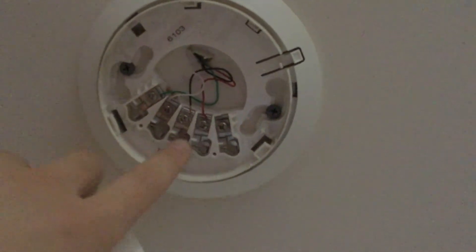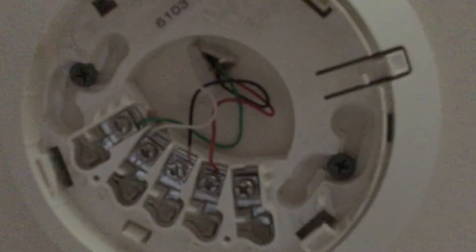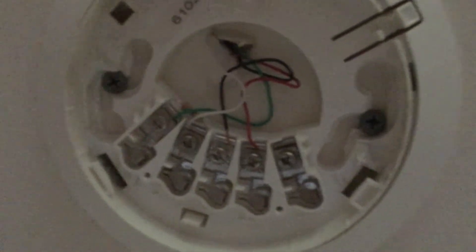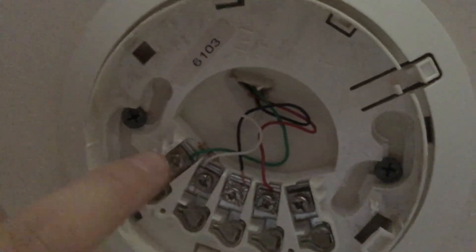We have these: these are the power and this is the alarm. There's the resistor on it. And this, guys, is how you correctly wire up an end-of-line resistor. You're supposed to have it at the end of a circuit. Everything runs in a series, otherwise you get overcurrent trouble. And you have another resistor on these two. Let's give this another blow.